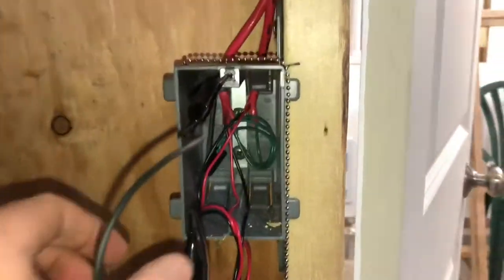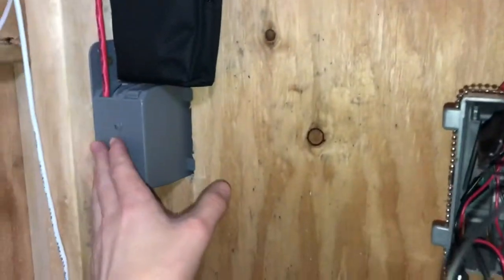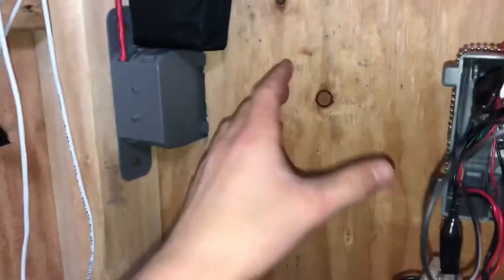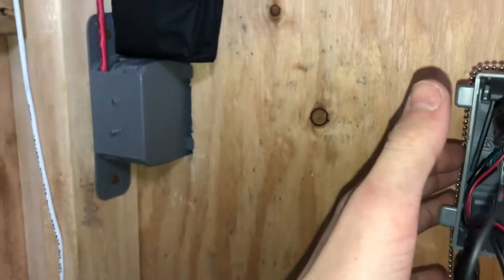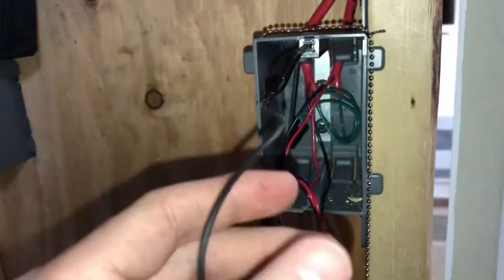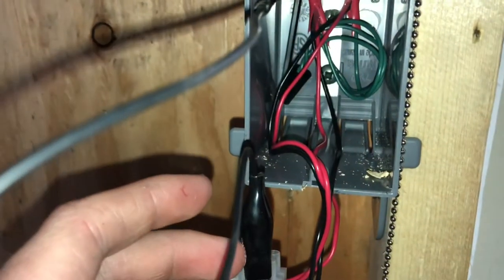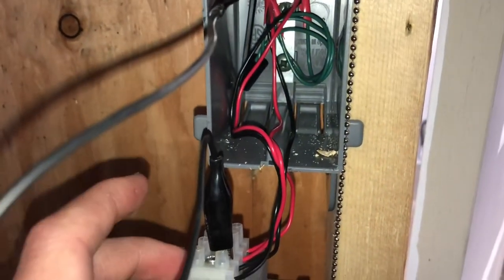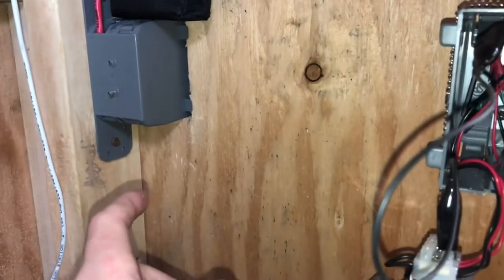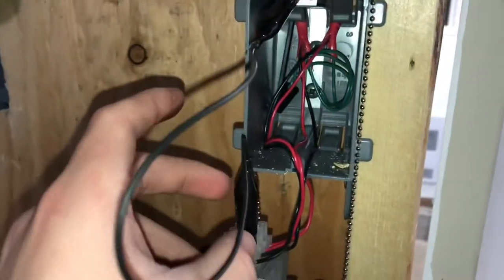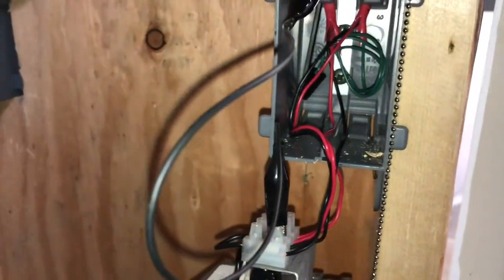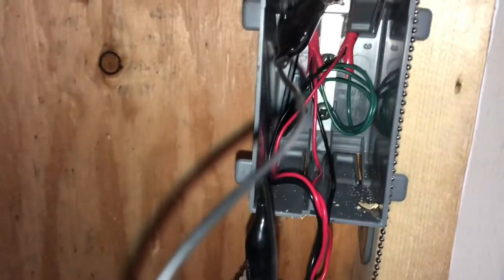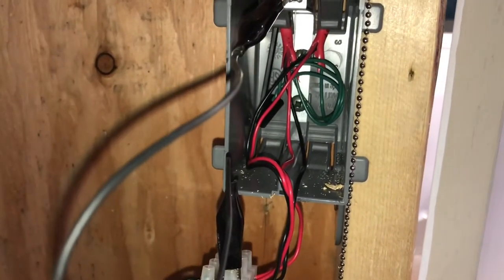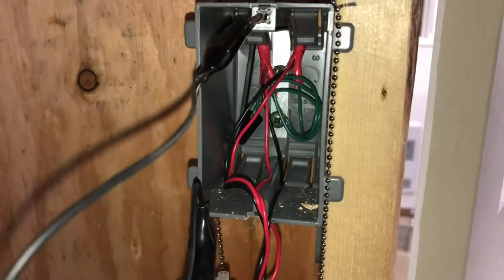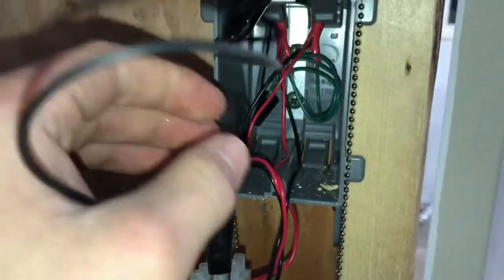But the situation could also be that inside a conduit, assuming this was in a conduit, that is our end of line device, but there could be 20 more in between this device that has the fault on it and your end of line. We don't need to think about that. It could be in the pipe in between this device and your next device. So let's say you go to your next device and you meter both sides, but we already know what's on a negative, and you meter your line side or your incoming side and you get continuity between it and ground. And on the outgoing of this one, you got it between it and ground.